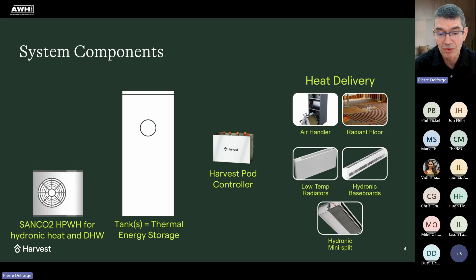And so far, we've only talked about the heating side, and we provide cooling as well, and a little different. So for cooling, because the Sanco 2 only provides heat, so heat pump water heater, not an air-to-water heat pump, we need to integrate with a separate air conditioner or heat pump, which is a regular air-to-air heat pump for cooling and for supplemental heat. So we can also use the heating cycle of the heat pump, if it's a heat pump, to provide supplemental heat and augment the capacity of the Sanco 2 heat pump to go up to 4 tons of heating capacity, where the hydronic system will always provide the first 2 tons, and then anything above that will be provided by the supplemental heat pump.